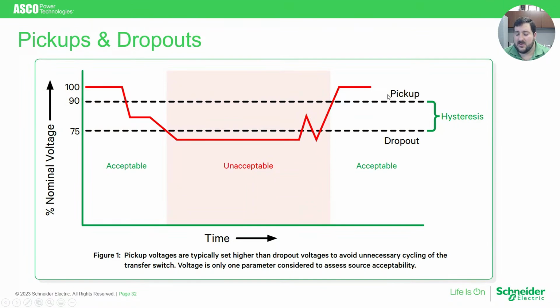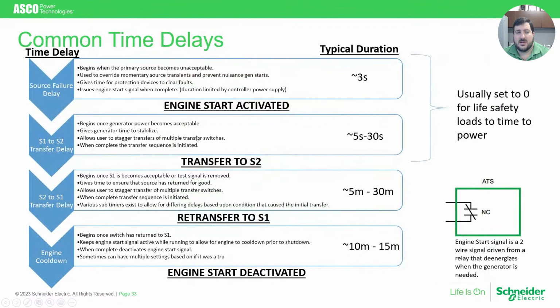Just like a thermostat at home, where you do not want to start and stop the air conditioning every 5 seconds because you set the temperature at 70 degrees and now it's 70.1 or 69.9. So that provides a greater level of control. And even though this diagram is based on nominal voltage, the same concept can be applied to over voltage, to frequency, and everything overall. A common transfer sequence has many steps to it.